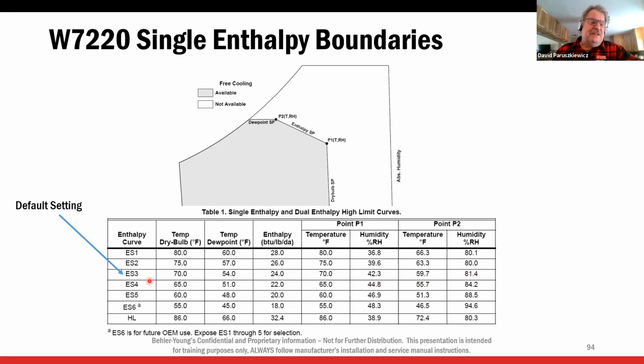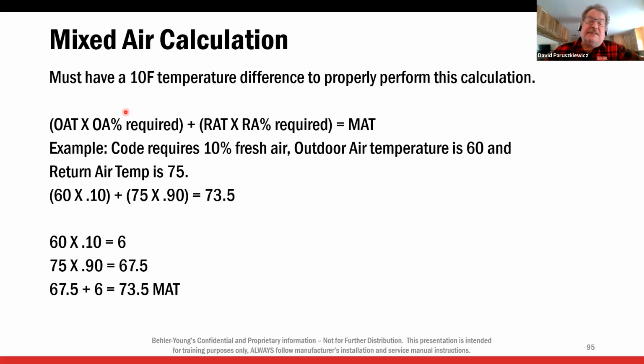Now, normally we can leave that default alone, all right? Again, that's why you always want to use a two-stage thermostat, because in the event the economizer is open, because 70 degrees, 42% humidity, and for some reason we still can't cool the space, we are still going to allow the compressor to come on, even on a single stage unit. So you normally shouldn't have to change this setting. That's the factory default.